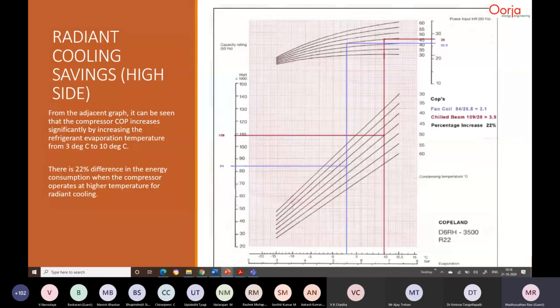And this can be validated. I don't have it right now in front of me, but if you can imagine the pH diagram, the higher you take the evaporating temperature, the suction pressure will also go up, and there will be less area under the graph in your typical refrigeration cycle. If you draw it on a pH diagram, you can see the difference. Unfortunately, I don't have it here, but that is what happens. So between this and the elimination of the fan motor, that's why I said you save somewhere between 30 to 50%. And that's a lot because in buildings, air conditioning is the biggest guzzler of energy. So if you can reduce 30 to 50%, that is a significant reduction in energy consumption.